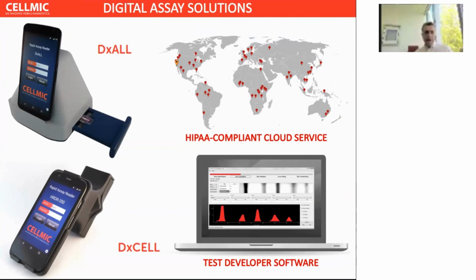So from the perspective of the reader, who's going to pay for the test? It's the same. These tests are prescribed depending on the condition. Some of them are reimbursed, some of them are not, depending on the patient and your insurance and what those tests are looking for. From the reader point of view, it doesn't matter. Let's say there are certain tests that are FDA approved or that are going through the FDA. The idea here was the test developer, the test manufacturer, if they want to have a reader for quantitative analysis, they would go through the FDA approval of their biomarker detector, their rapid test with our reader, so that they lock the reader, they lock their chemistry, they lock their software, so that everything as a combo goes through the FDA. If you don't do that, then every time you change your reader, you have to go through the FDA again, even if your chemistry remains the same.